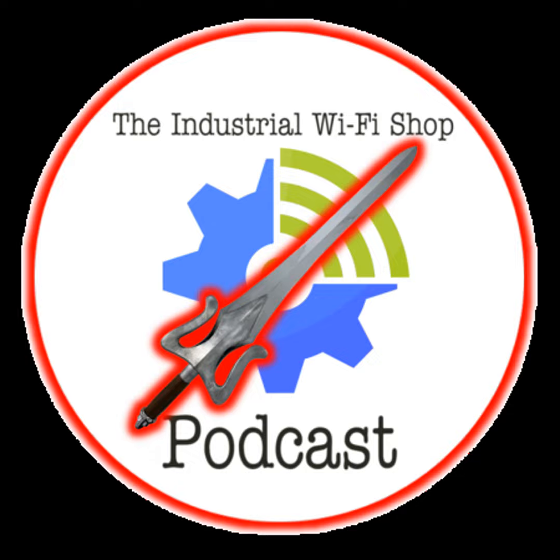This communication is pretty much, at its simplest form, electrical impulses. But it's not really encoded like Ethernet data is, because you're looking at either analog or digital signals. The analog signals are usually like 4 to 20 milliamp, where 5 milliamp means one thing and 15 milliamp means something else. It's really interesting how all of that is configured. But really wireless I/O is the same thing, with the exception that it's not backhauling across solid core copper or fiber, it's backhauling across a wireless medium.